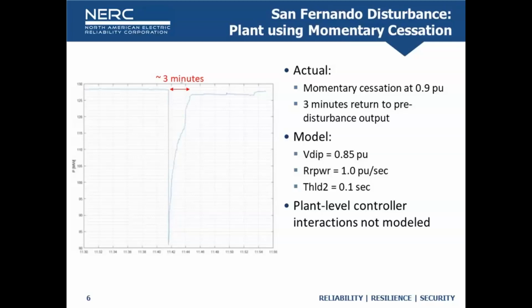Some inverters tripped at this facility that I'm not going to get into that level of detail, but in essence, the model says the resource should come back in 1 second, and the resource is requiring 3 minutes to come back to pre-disturbance values. So that's obviously a concern, and it's attributed very likely to the plant level controller interacting with the inverters, and that's not modeled in the positive sequence dynamic models that we use.